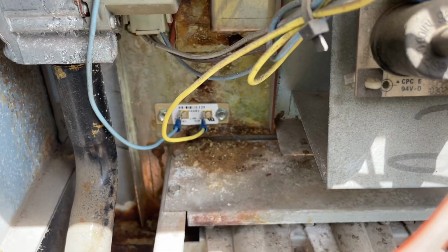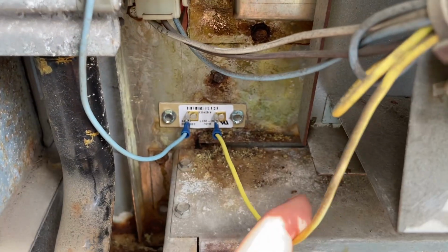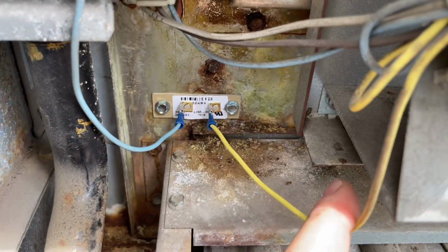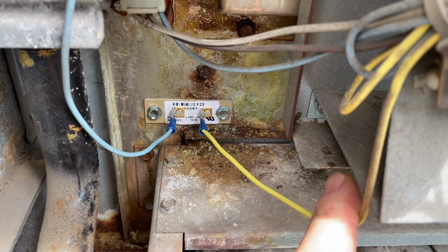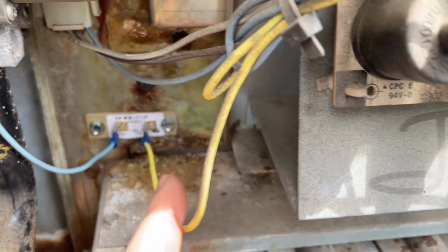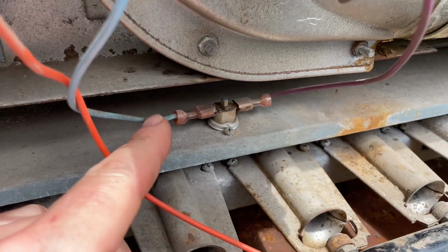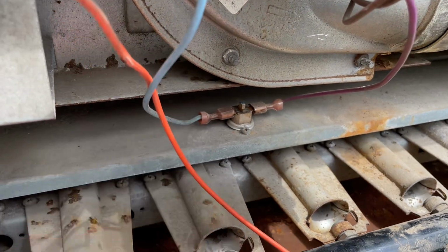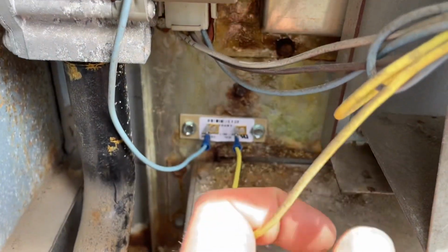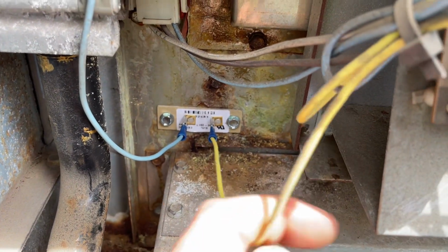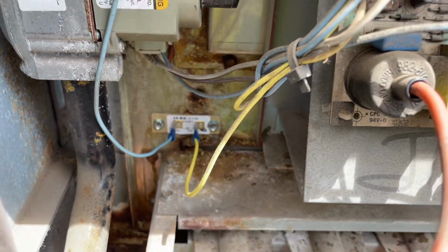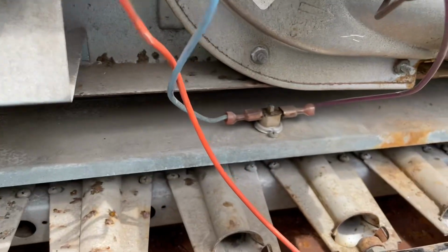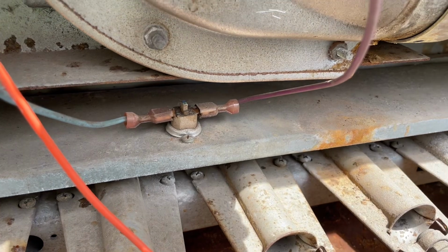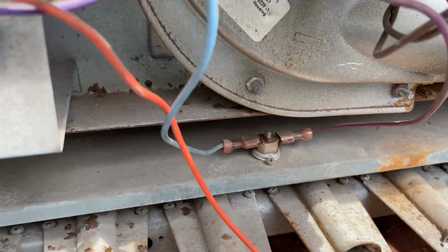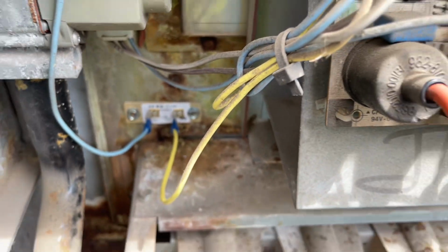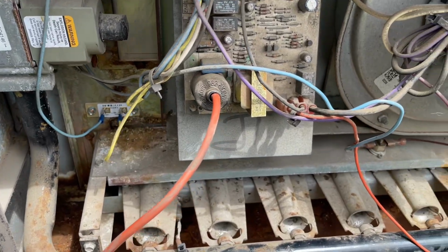Oh, and by the way, guys, forgot to mention before, if you ever come across any sort of limits for heating equipment, whether it be a primary high limit, a secondary, rollout, it doesn't matter, a flow switch or a boiler, you can jump these out for testing purposes only like I did before, but never leave site with these jumped out. You can cause a world of problems. So that's just a little tech tip there, guys. Never, ever leave heating safeties jumped out.